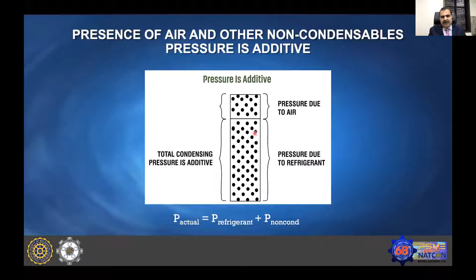How can we understand if there are non-condensable gases in our system, if we have air in our system? If you see a typical system, from the compressor, air and ammonia both enter the condenser. As the gas moves into the condenser and goes to the downside, the ammonia becomes liquid. However, air remains as it is because air does not get condensed here. So if we are able to measure the pressure of our receiver and the temperature of the liquid, and we convert that liquid temperature into the corresponding saturated pressure, then the pressure difference between the actual pressure and the refrigerant pressure can give you the pressure of the non-condensable gases. I'll repeat: the pressure in the actual receiver and the corresponding saturated pressure of the liquid in the receiver, the difference between the two is the pressure of non-condensable gases.